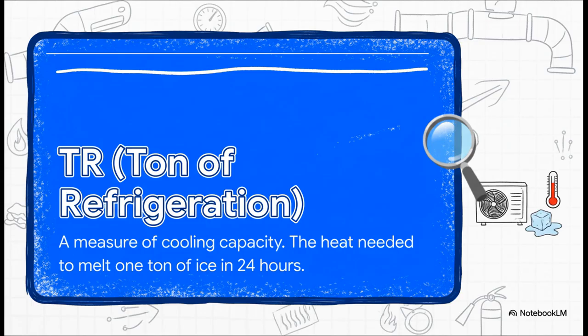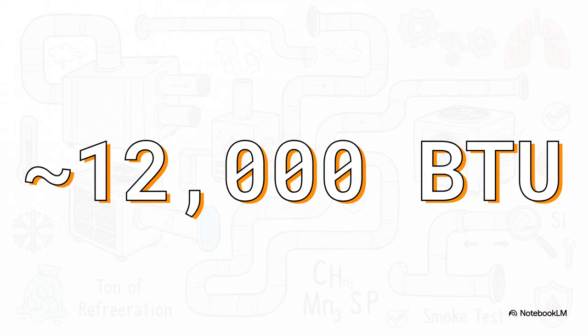Now this next one is a little weird, but I promise you it's brilliant. It's called a ton of refrigeration, or TR for short. Now this has nothing to do with weight. It's all about cooling power. Get this. 1 TR is the amount of heat it takes to melt 1 ton, a literal ton, of ice over a 24-hour period. What a cool way to think about it, right? And just to put a hard number on that, for all my fellow nerds out there, 1 ton of refrigeration is equal to about 12,000 BTUs per hour. That is a ton of heat, no pun intended, being yanked out of the air every single hour.